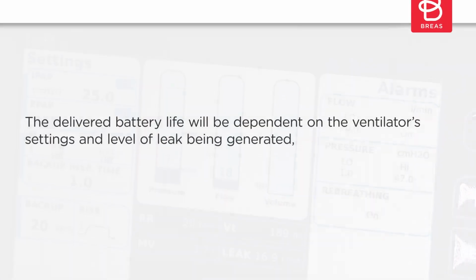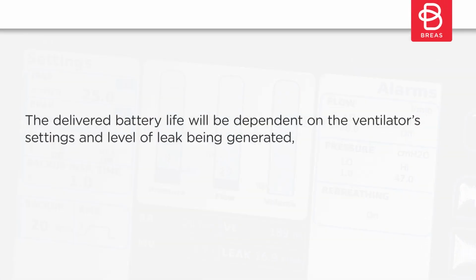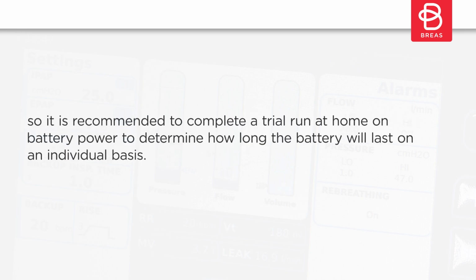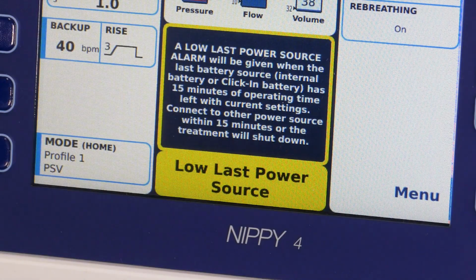The delivered battery life will be dependent on the ventilator's settings and level of leak being generated, so it is recommended to complete a trial run at home on battery power to determine how long the battery will last on an individual basis. The device will alarm to indicate when the battery is at 50% and also when it is reaching a critically low level.